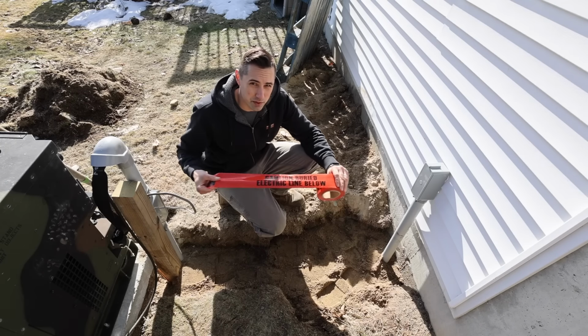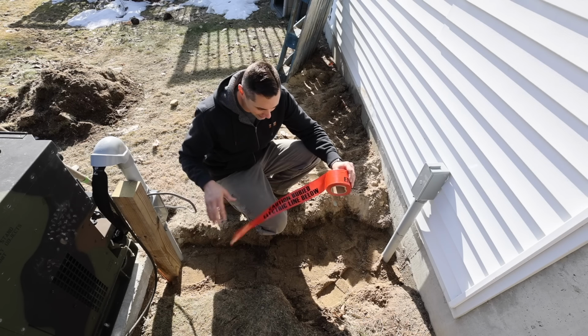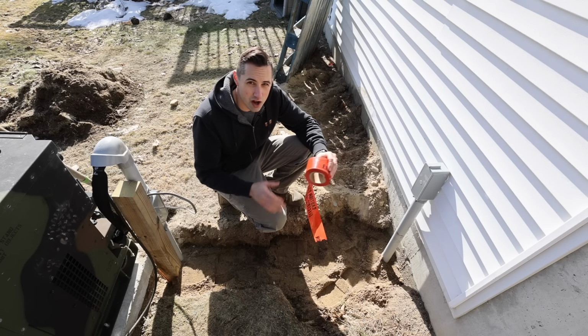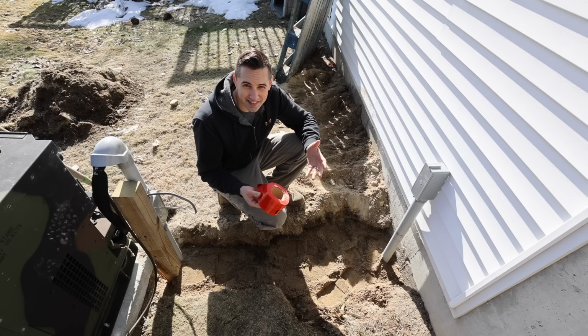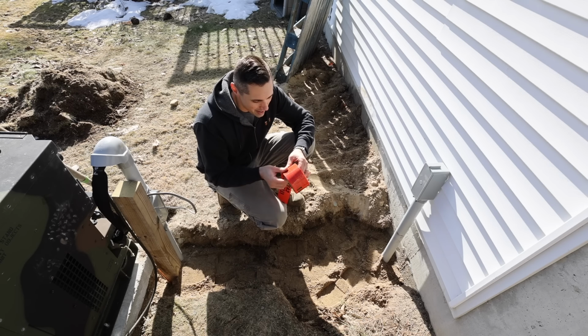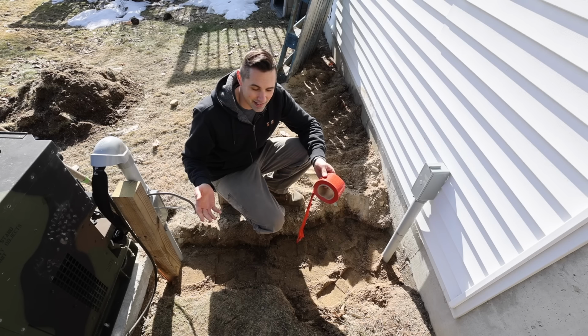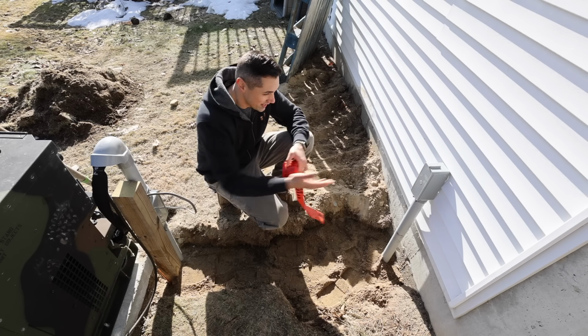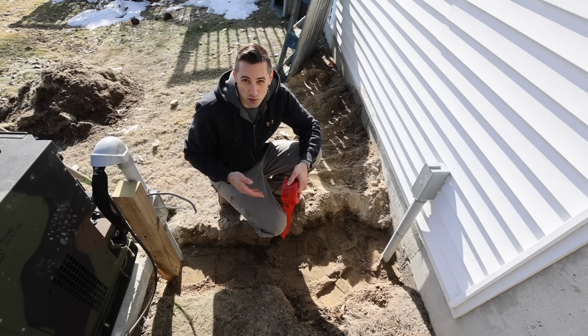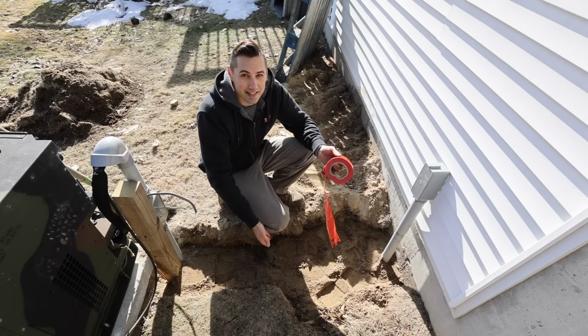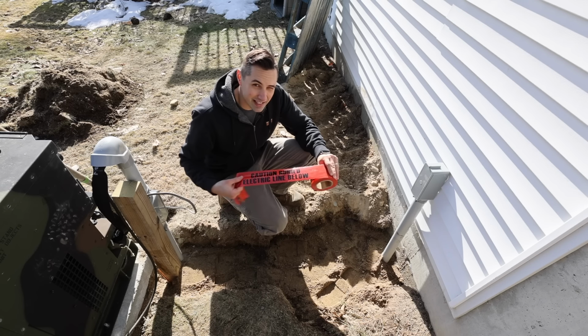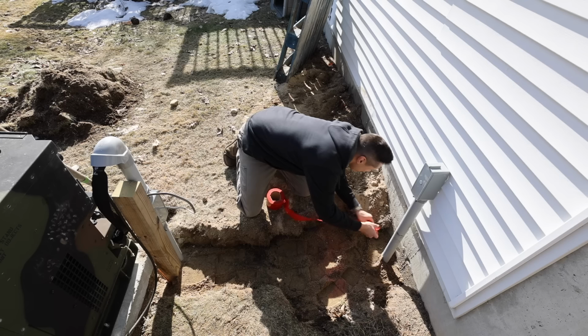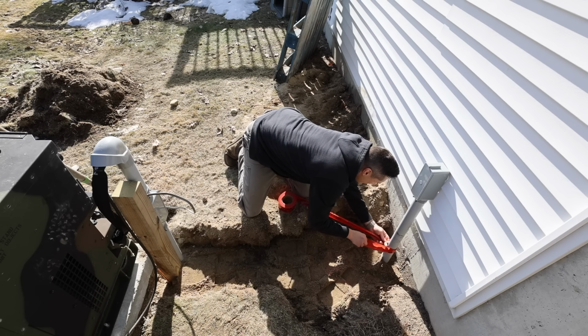Technically I'm supposed to bury some of this marking tape at least 12 inches above the conduit. The purpose of this is so that it doesn't get dug up accidentally. Now it's a little bit silly in this case because it's a short run. You can see where it goes in and where it comes out. So where do you think the conduit is? Obviously it's in the middle, but it is technically required, so I'm just gonna do it. Maybe I just tie it to this.